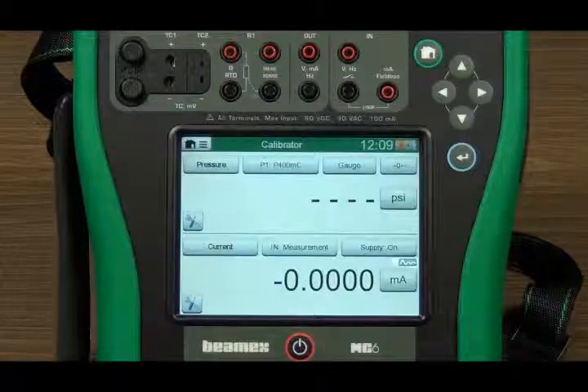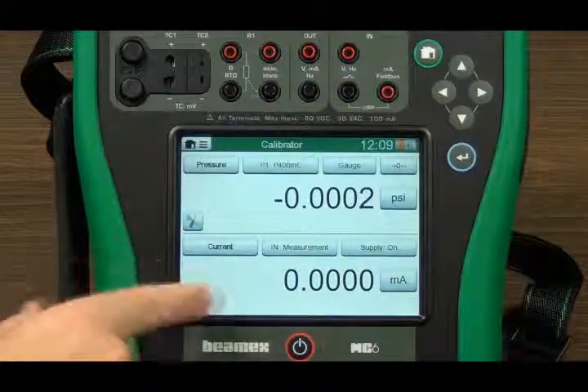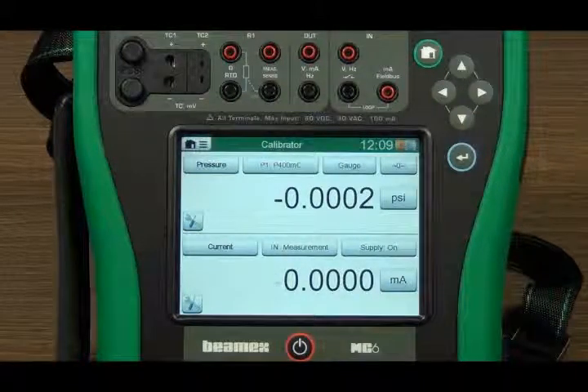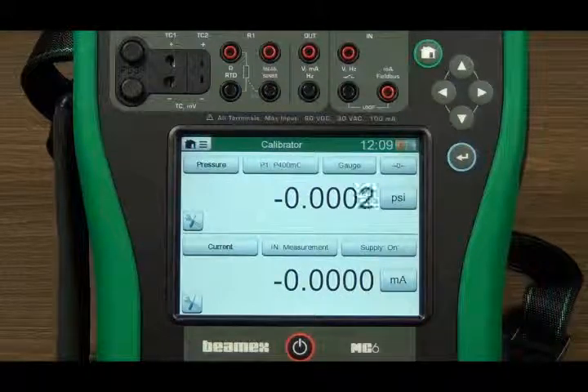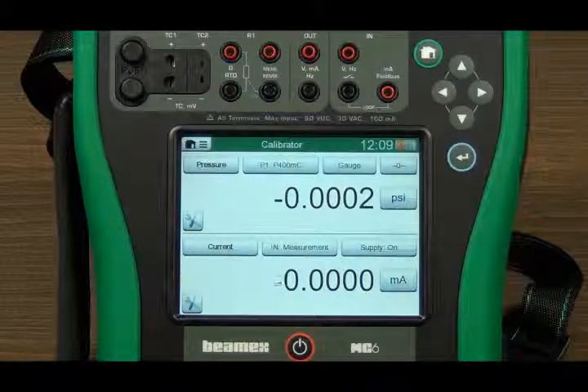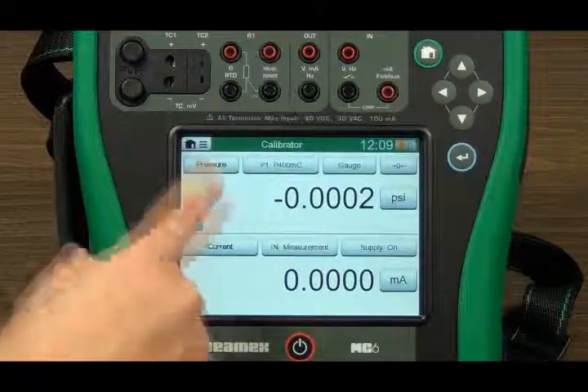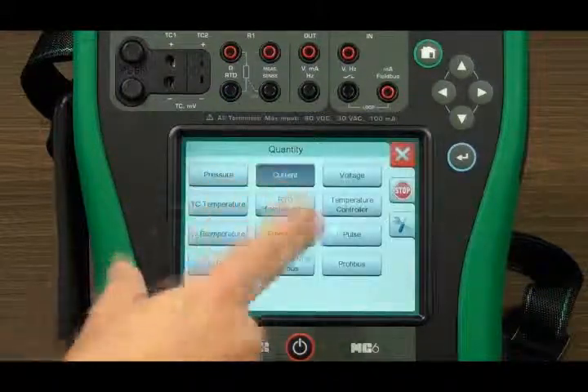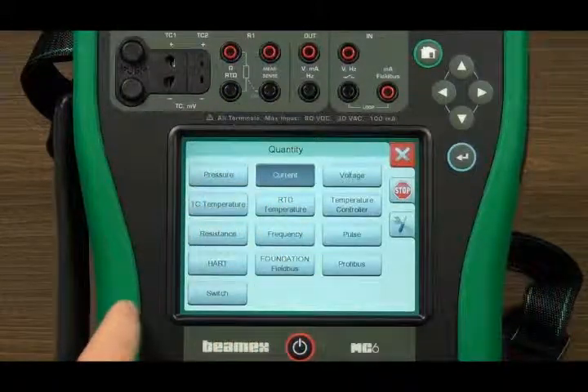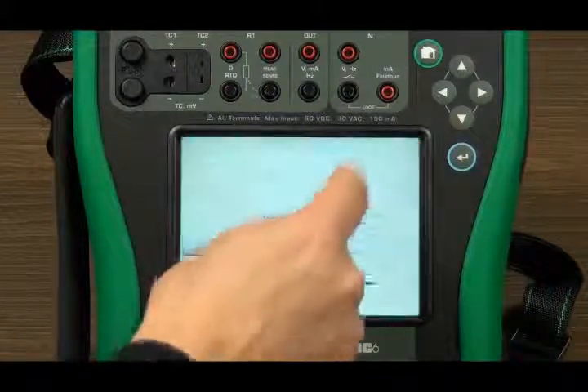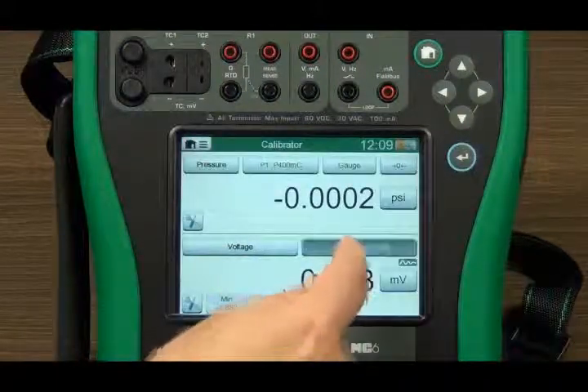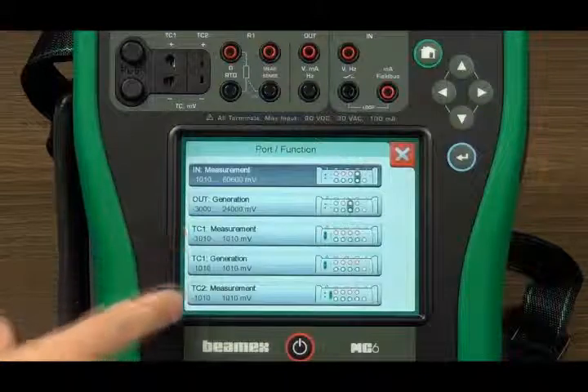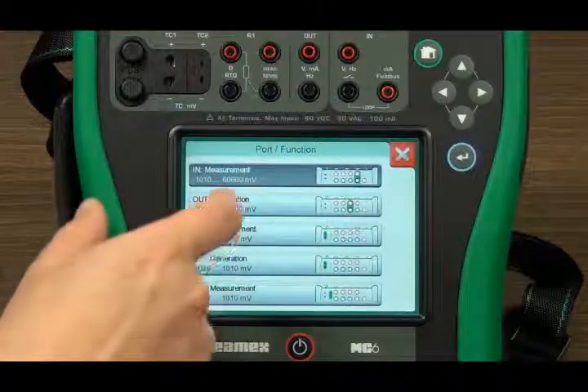Calibrator. The calibrator mode has a dual display for 2 simultaneous measurements or generations. Its main purpose is to check and calibrate various process instruments. The first button is for selecting quantity. Touching it shows all available quantities. Touching the next button will show you a list of available functions for measurement and generation. Also, a connection diagram will be shown to illustrate where to make the connections.